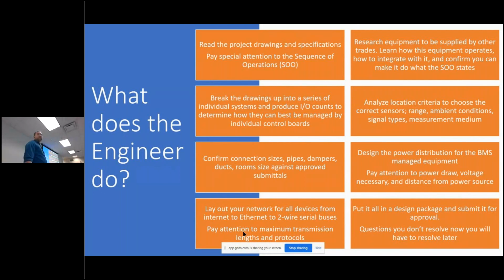Something the engineer has to pay special attention to is the sequence of operations - essentially a written narrative about how everything in the building is going to work. At 8 in the morning, when the building goes into occupied period, all of the zones change their temperature set points to match whatever occupants are expected to want. When the building goes into unoccupied period, say at 5 p.m., maybe it drops down to something lower, 60 or 65 degrees, because heat costs money and we want to spend less. So we let the building drop down to a lower energy-consuming state - maybe we'll turn off equipment that doesn't need to run, or turn off lights that don't need to be on.